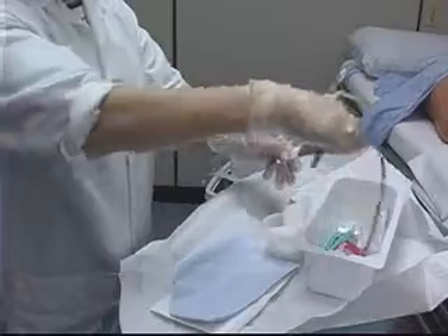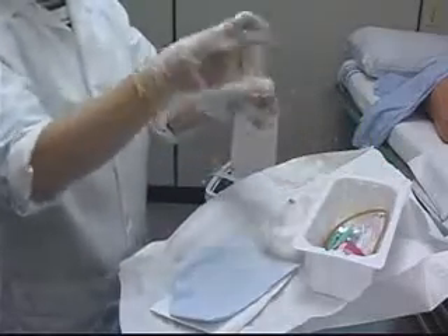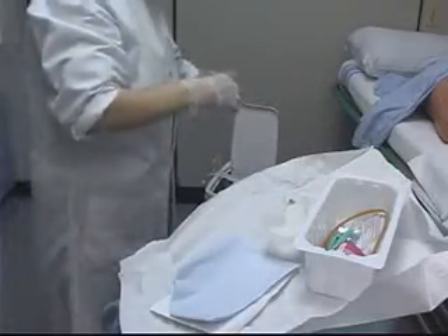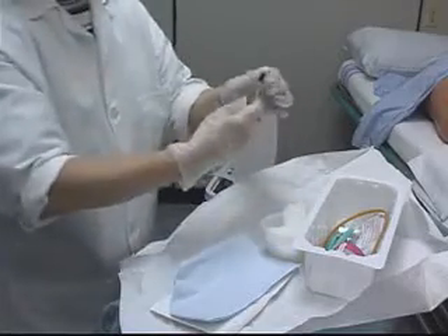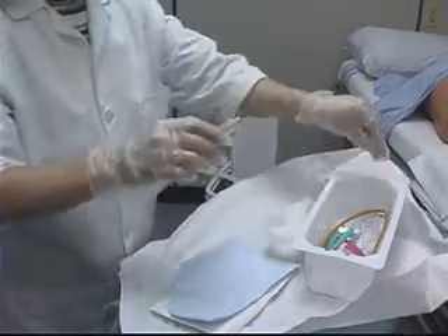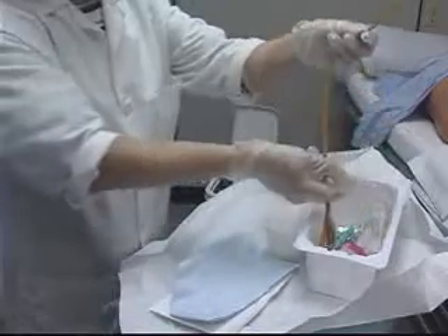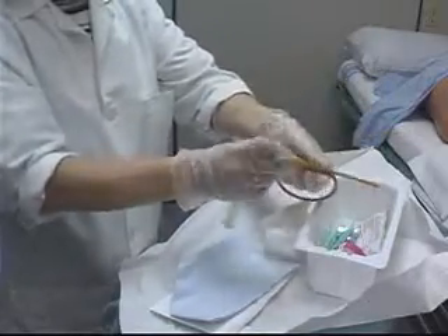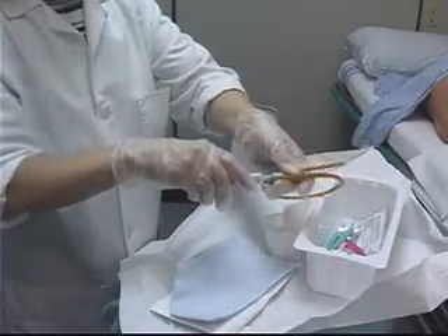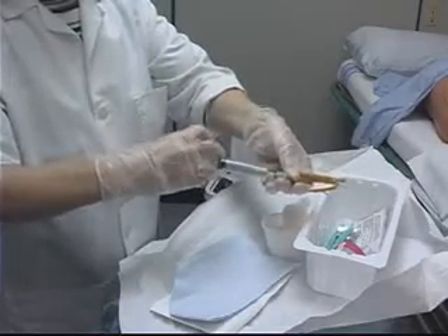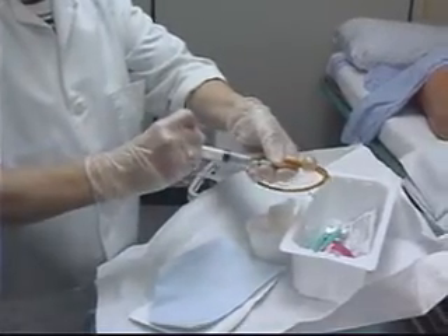With respect to the catheter, local hospital policy, as well as the recommendation of the supplier, is to check the patency of the catheter balloon by inflating it using the pre-filled syringe from the tray. If the balloon inflates, make sure it will also deflate. When this is done successfully, put the syringe to the side.